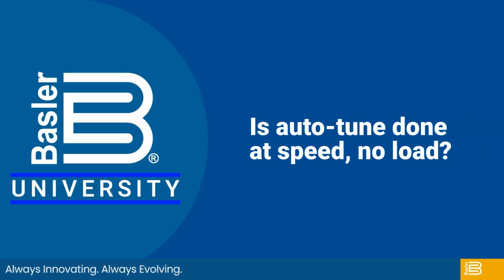So is the auto tune done at rated speed, no load? Yes, that is correct. It is important to make sure the generator is at rated or nominal speed and you have no load on the machine. As I mentioned, one of the first steps of the auto tuning process is that it shuts off excitation. So you don't want to be supporting load or be tied to another machine while you're doing the auto tuning.